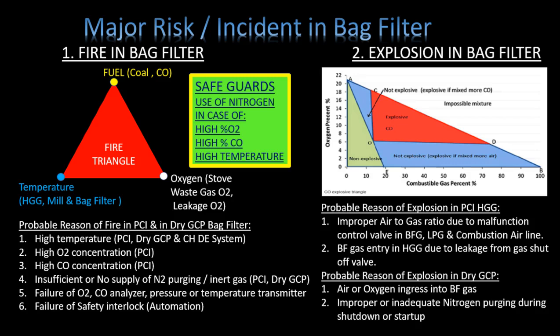Probable causes of fire include: high temperature, applicable in PCI, dry GCP, and cast house dedusting; high oxygen concentration in PCI; high carbon monoxide gas concentration in PCI; insufficient or no supply of nitrogen purging or inert gas in PCI and dry GCP; failure of oxygen or carbon monoxide analyzers; failure of pressure or temperature transmitters in PCI; and failure of safety interlock automation in PCI and dry GCP.